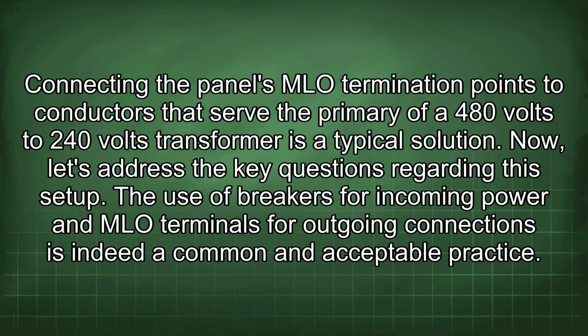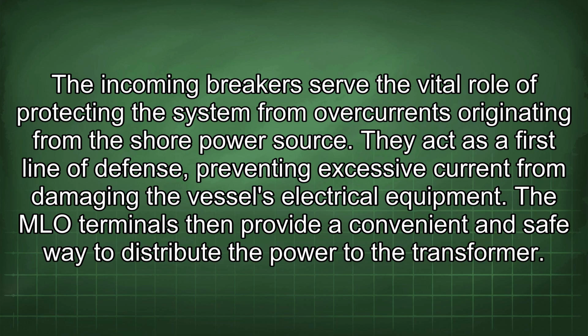The use of breakers for incoming power and MLO terminals for outgoing connections is indeed a common and acceptable practice. The incoming breakers serve the vital role of protecting the system from overcurrents originating from the shore power source. They act as a first line of defense, preventing excessive current from damaging the vessel's electrical equipment. The MLO terminals then provide a convenient and safe way to distribute the power to the transformer.